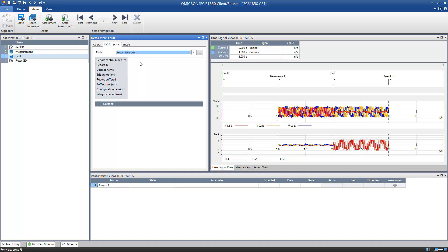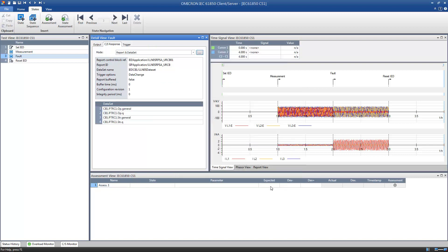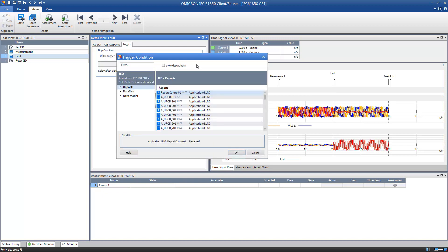Remember that only reports that have been activated previously in the state Set IED can be assessed. Choose the report that has been activated in the state Set IED. You can define a trigger to end the state before the time of the state has run out. You can either choose a change in the data model or a change in the data set of the report to be the stop condition. In our example, we select the receipt of a report as the trigger.